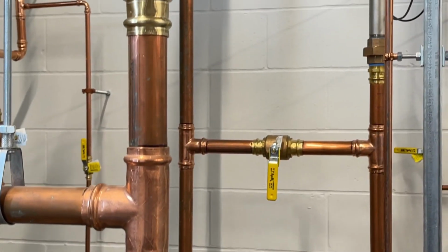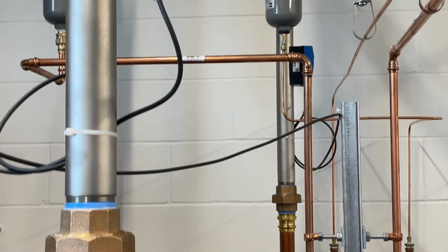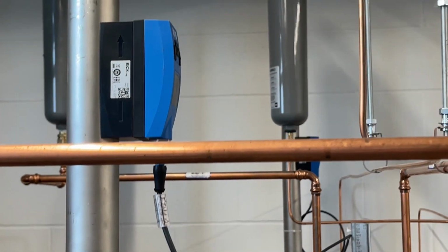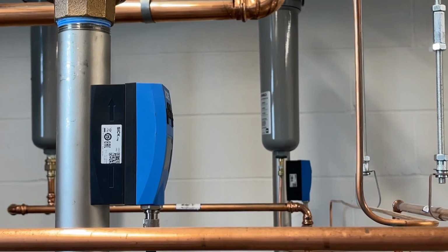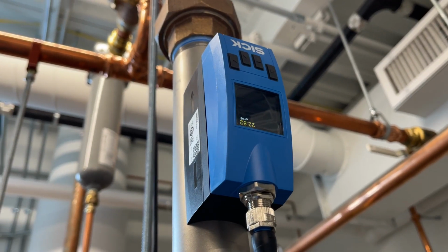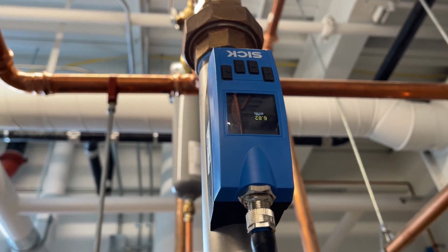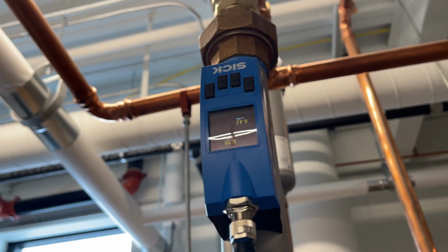Based on these principles, we've installed our FTMG gas flow meters on the supply side of our compressed air system. This allows us to confidently know what we are generating, verify that our system is operating as designed, and flag leakage. Our next step is to add these same flow meters to the production cells behind you. This will enable us to drill down to each production cell and identify usage, narrow down leak detection, and enable us to calculate compressed air cost allocated to each individual production cell.